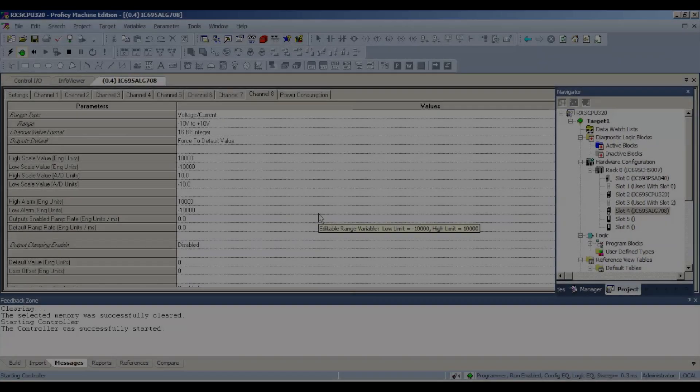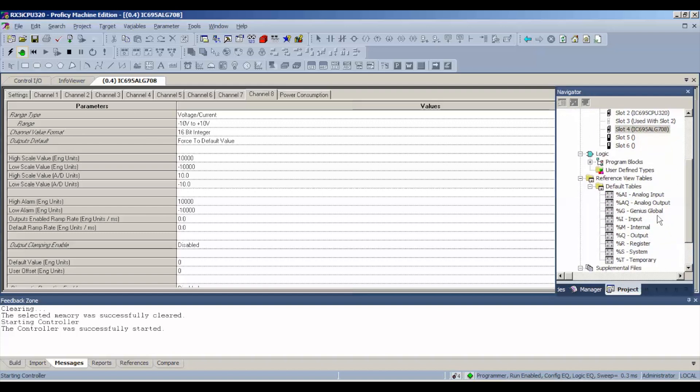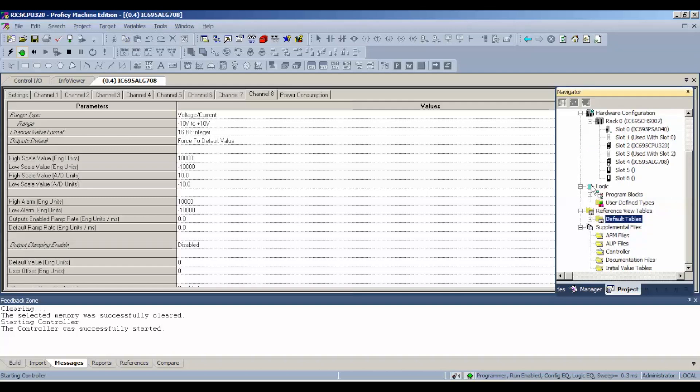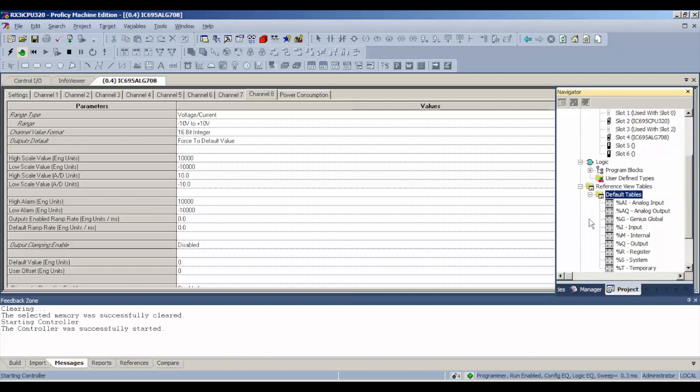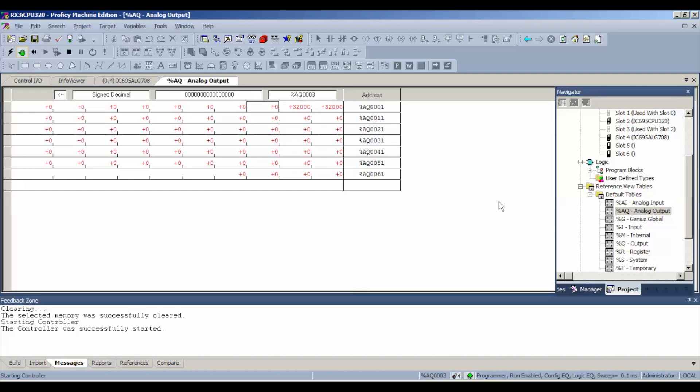Now everything is run enabled. That refers to our outputs are now enabled. We can use them. Configuration and logic are equal. We're going to go down to our default tables. If you don't have this open, you just click and expand the default tables. Go to analog output and we're going to start with channel number 1. That's why that reference address is important. I'm going to put a value that should yield 10 volts to begin with on each channel.